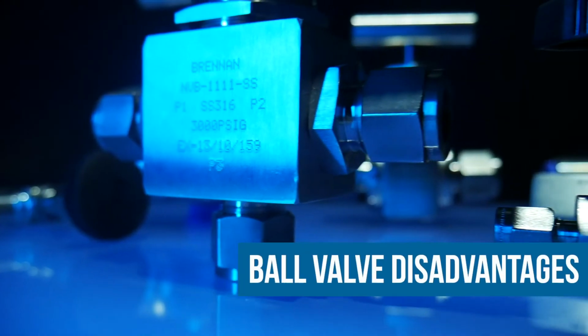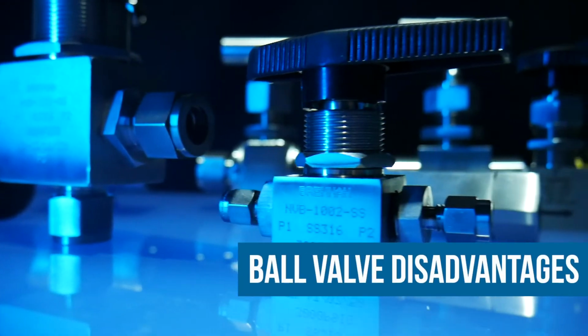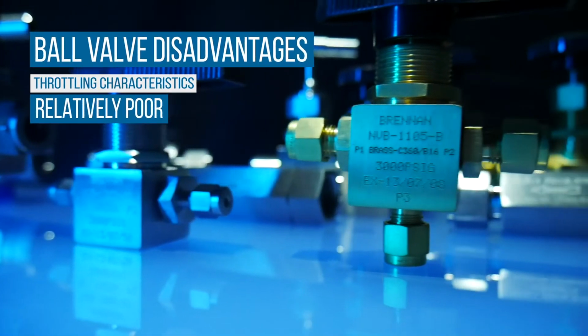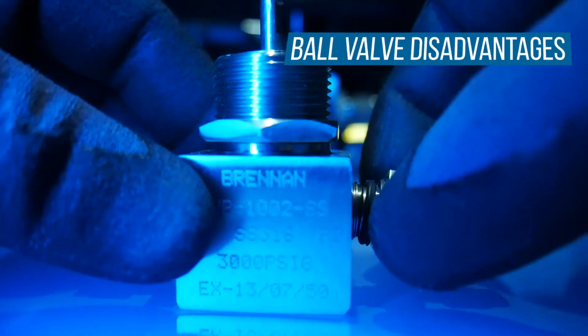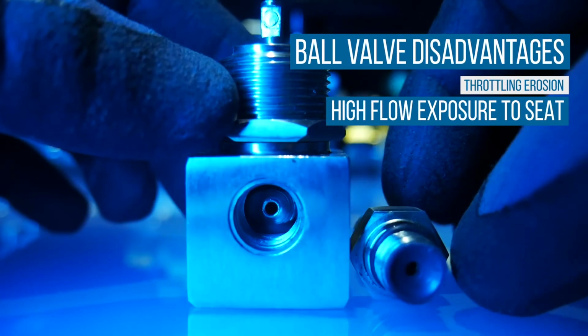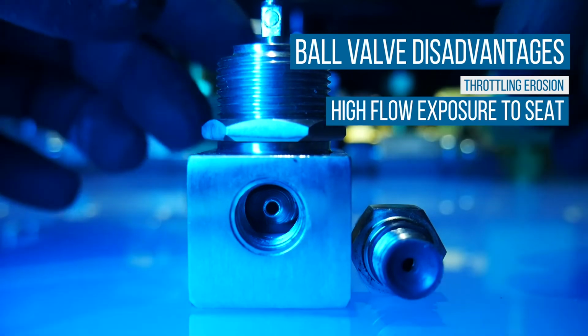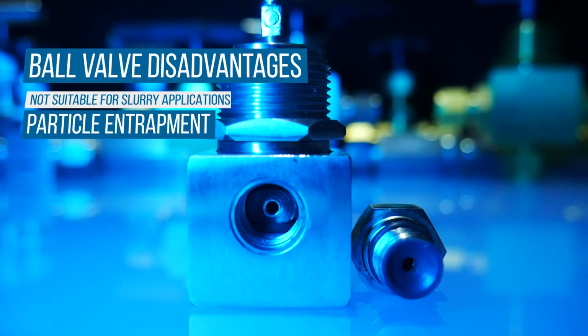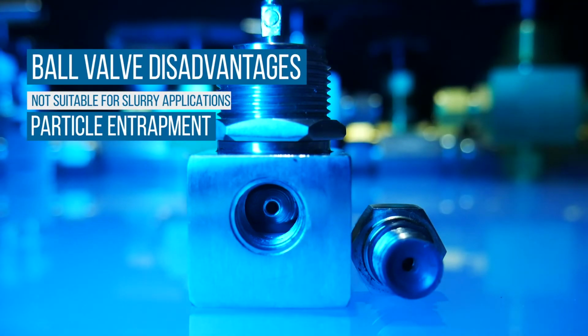There are disadvantages related to instrumentation ball valves. The ball design offers relatively poor throttling characteristics. The throttling position can lead to rapid erosion due to the seat's exposure to high-velocity flow. They are not suitable for slurry applications, as the entrapment of particles in the valve's ball and seats leads to wear, leaks, or failure of the valve.